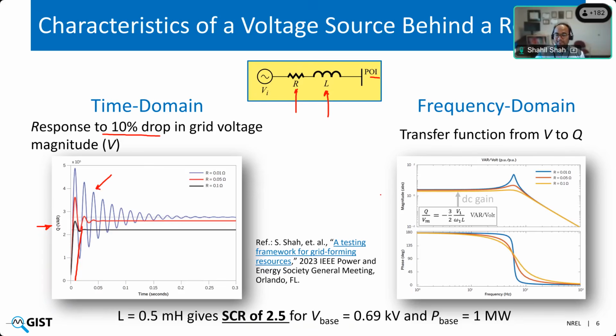And if we derive the transfer function from voltage magnitude at the POI to the reactive power output from the voltage source behind reactor, that is, the transfer function from V to Q, it turns out to be a second-order low pass filter, with the corner frequency being around the fundamental frequency, 50 or 60 hertz.